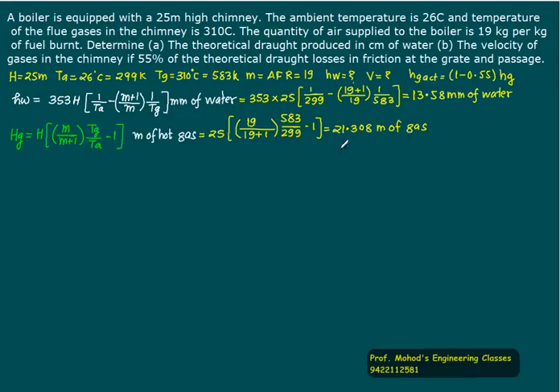This gives 21.308 meters of gas. Since 55% is lost due to friction, the actual available head for hot gas is (1 - 0.55) × hg = (1 - 0.55) × 21.308 = 9.588 meters. So actual draught available is only 9.588 meters.